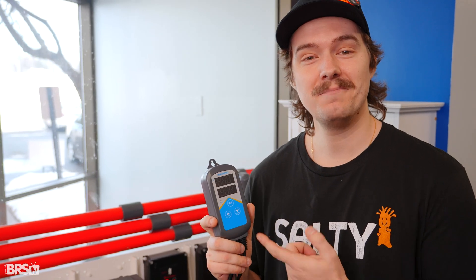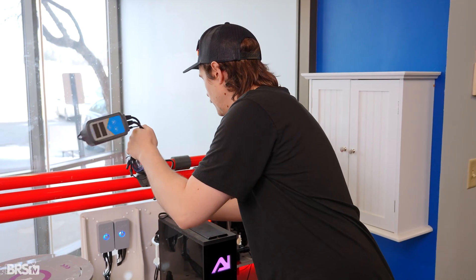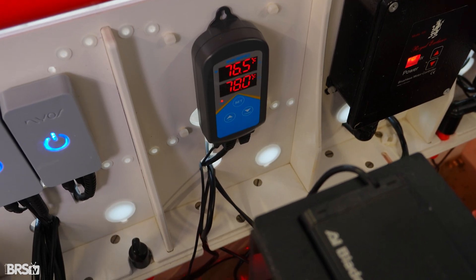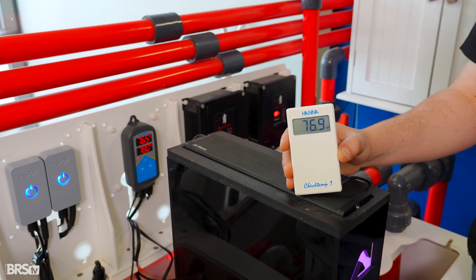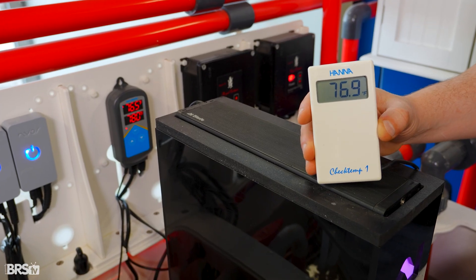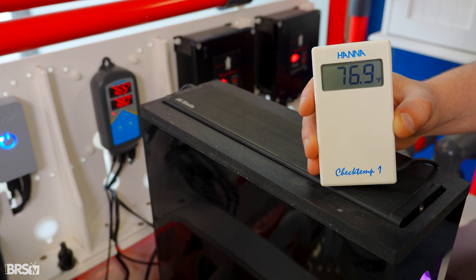Now we're going to get the Inkbird plugged in, mounted, and calibrated. I went ahead and grabbed our HANNA NIST-certified thermometer to calibrate the Inkbird. It looks like there are just a few decimal points of deviation, so I'm going to go ahead and get this Inkbird matching the HANA, and then we're good to go.